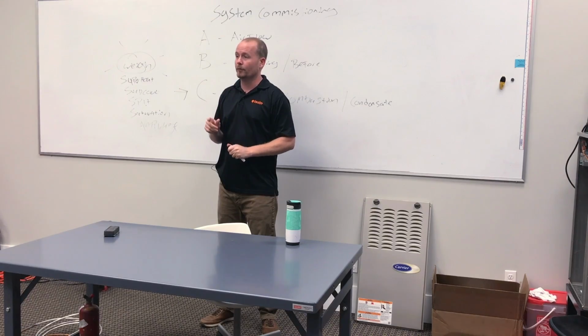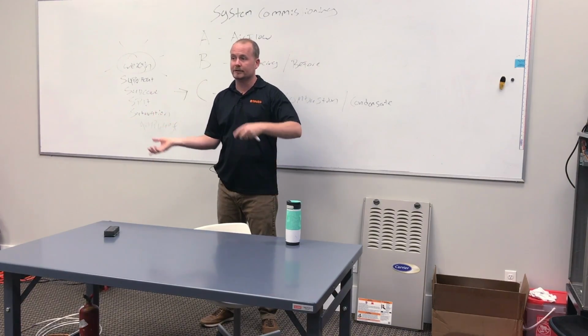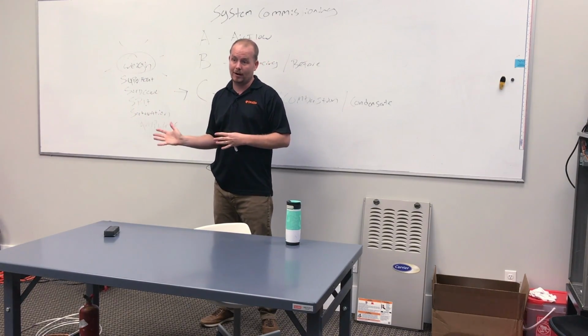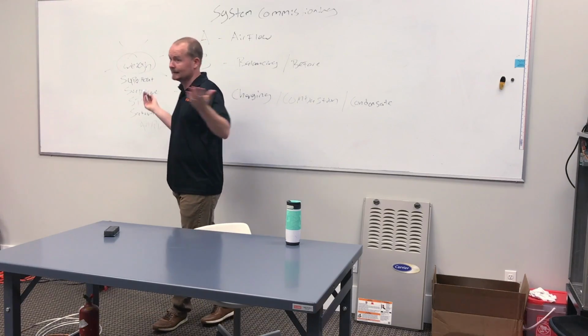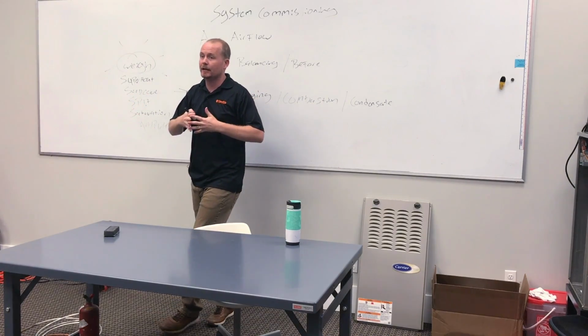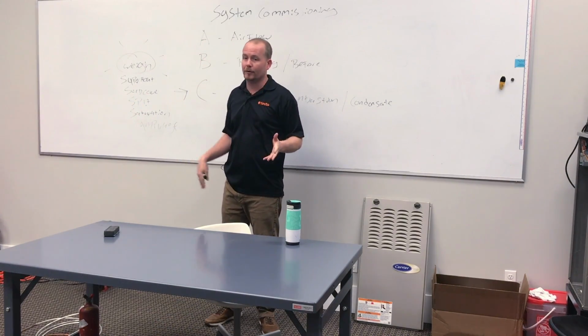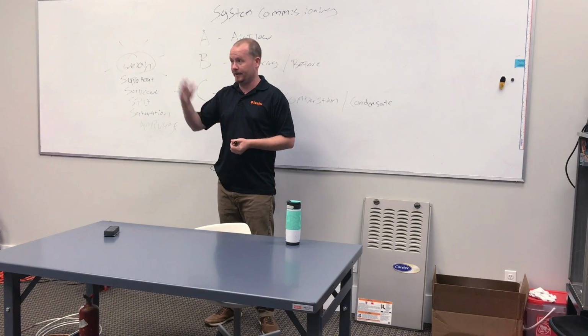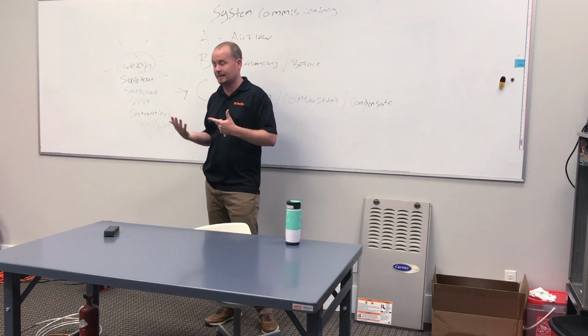This is especially important when you're doing light commercial stuff, 208 volts. Sometimes it's going to be low, and that's a big problem. So that's something to look for. Sometimes it's going to be high. We know this because we've installed a lot of these ICM 493s and we find out that they're going off because of high voltage, and that's something we have to deal with.